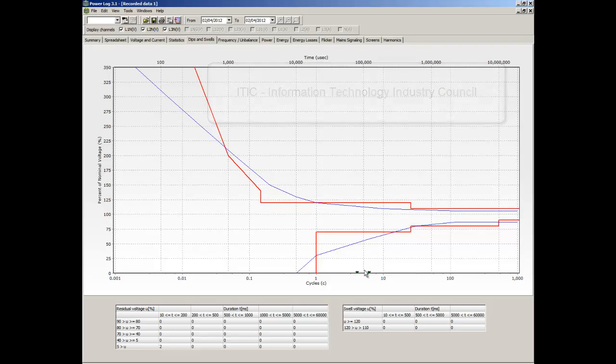If these events down here, we can see there's 2 small events which are down at the bottom. So this is where we had some dips, and on this table they're represented as being dips which went to less than 5% and lasted between 10 milliseconds and 200 milliseconds. These dips would possibly affect the equipment but wouldn't do any damage.